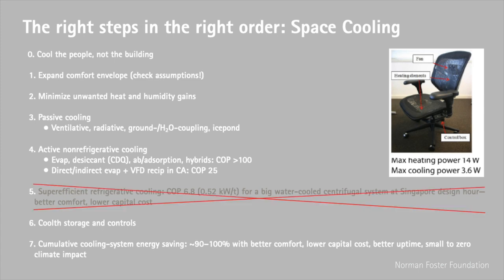But actually, we never need to get as far down the list as refrigerative cooling, and not even usually active non-refrigerative cooling either, to save 90 to 100% of the cooling energy with better comfort and uptime and lower whole system capital costs, even in the most severe climates. Most practitioners pursue these options in reverse order, worst buys first.